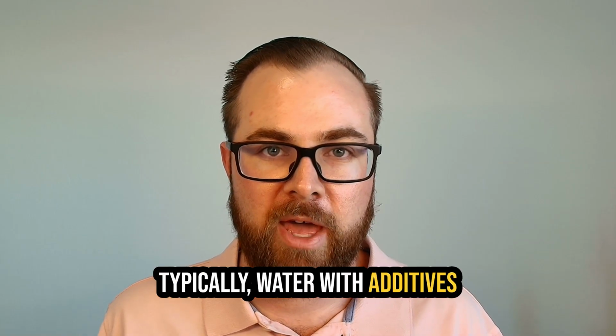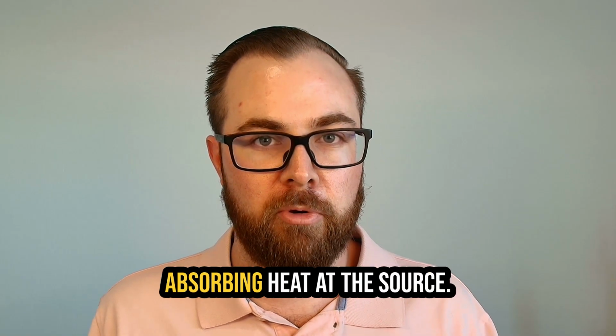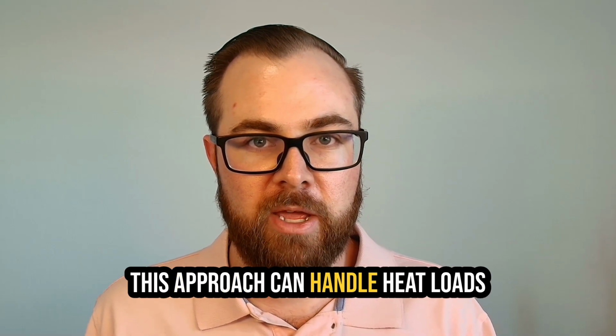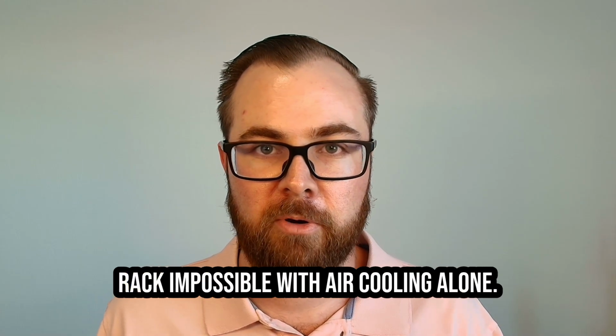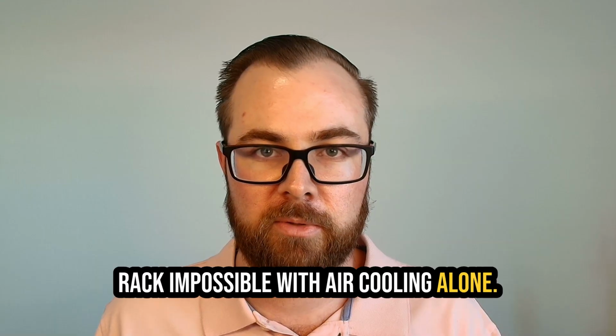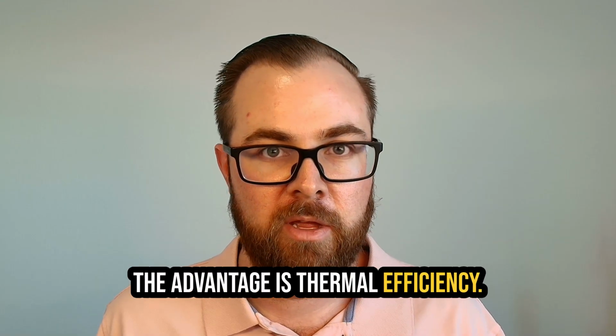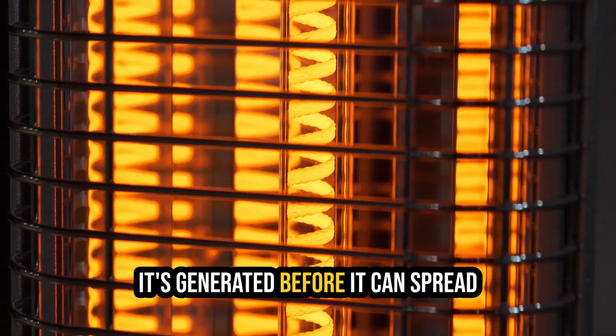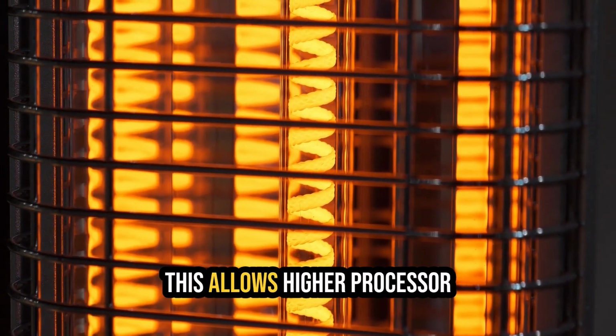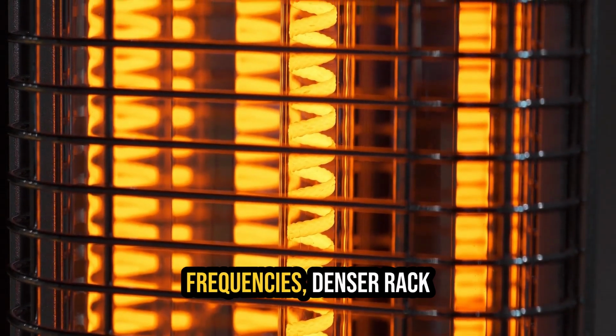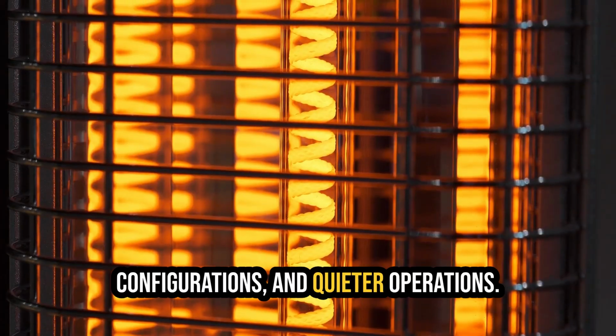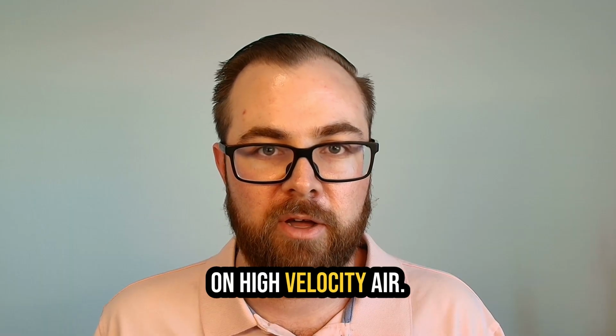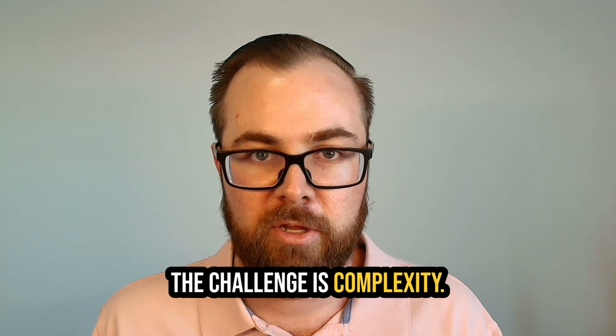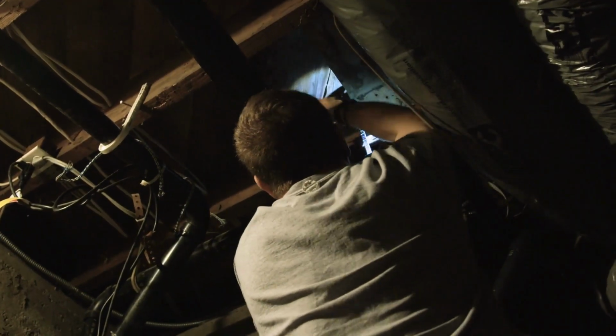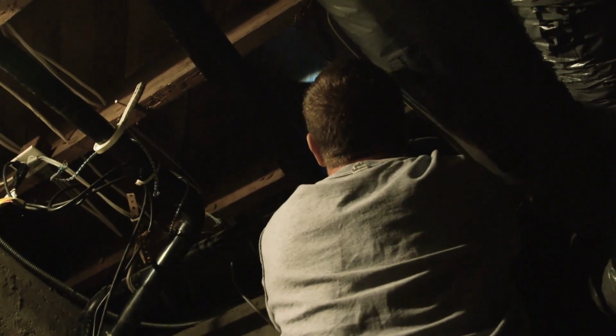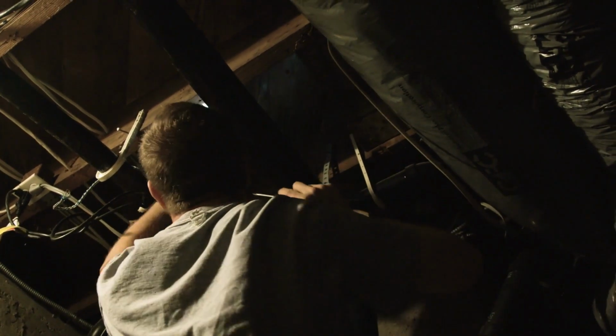Coolant, typically water with additives, flows through these channels, absorbing heat at the source. This approach can handle heat loads exceeding 100 kilowatts per rack, impossible with air cooling alone. The advantage is thermal efficiency. You're removing heat right where it's generated, before it can spread to surrounding components. This allows higher processor frequencies, denser rack configurations, and quieter operations since you're not relying on high-velocity air. The challenge is complexity. You need leak detection, redundant pumping systems, and careful maintenance. A coolant leak in a data center is a serious incident.